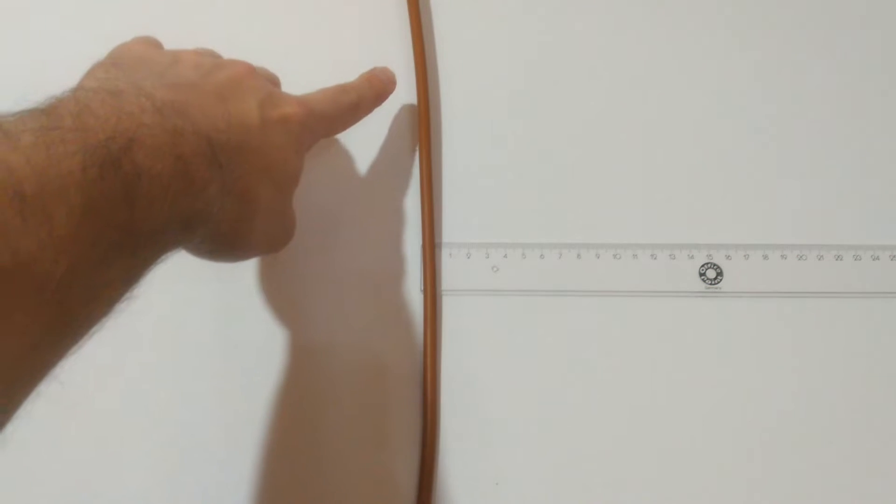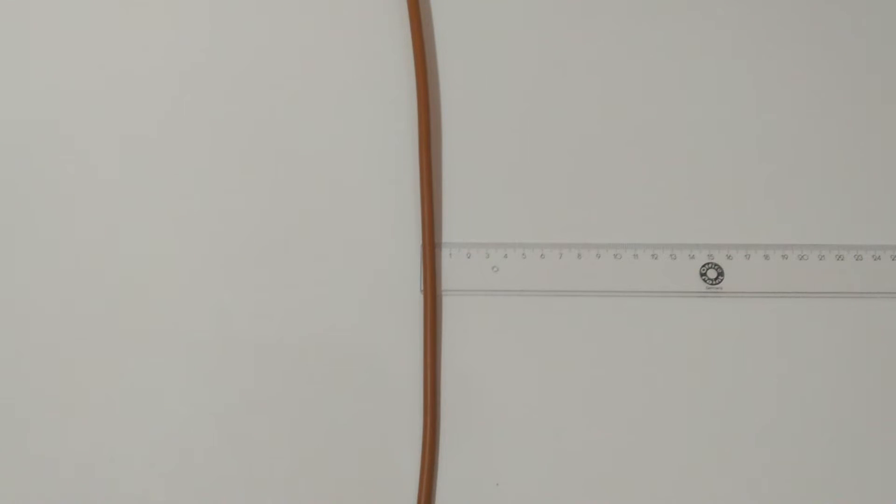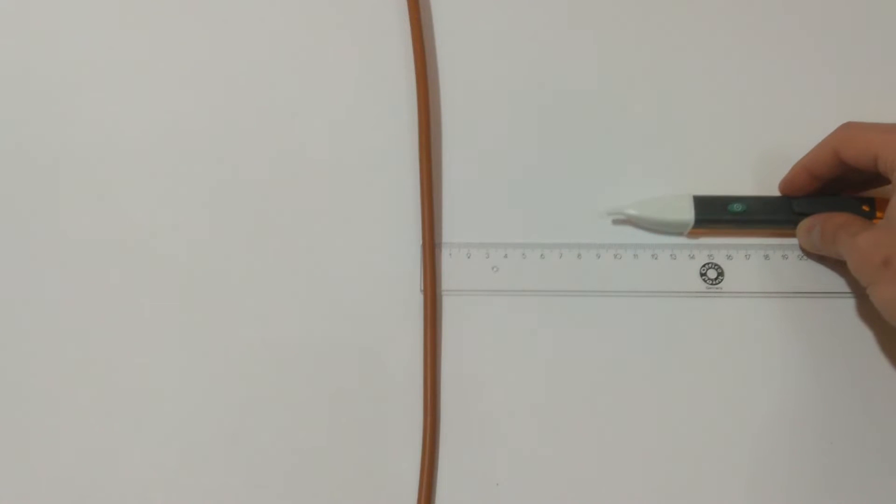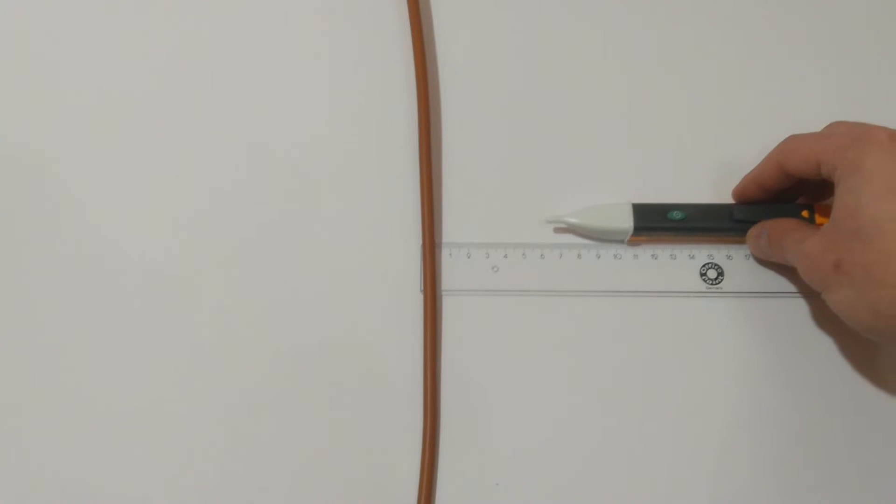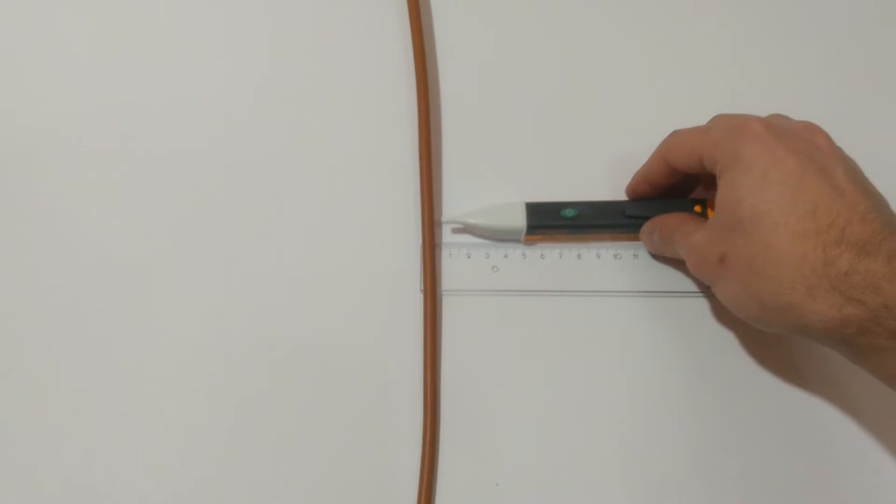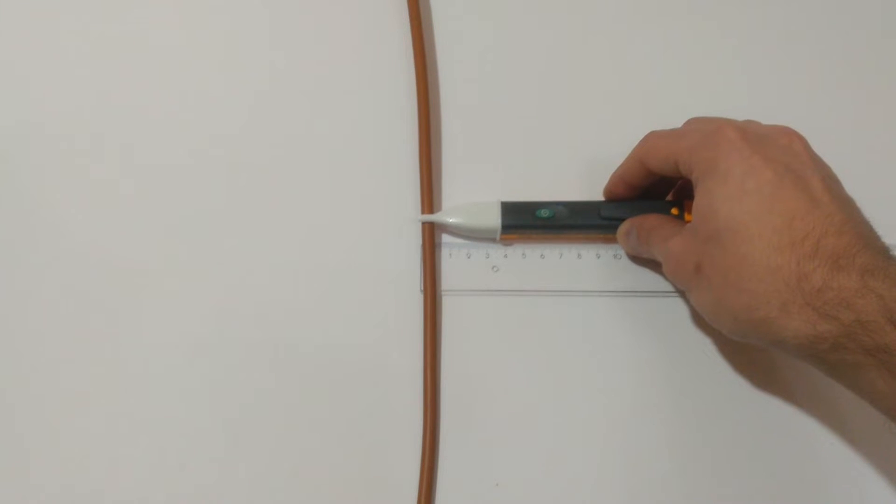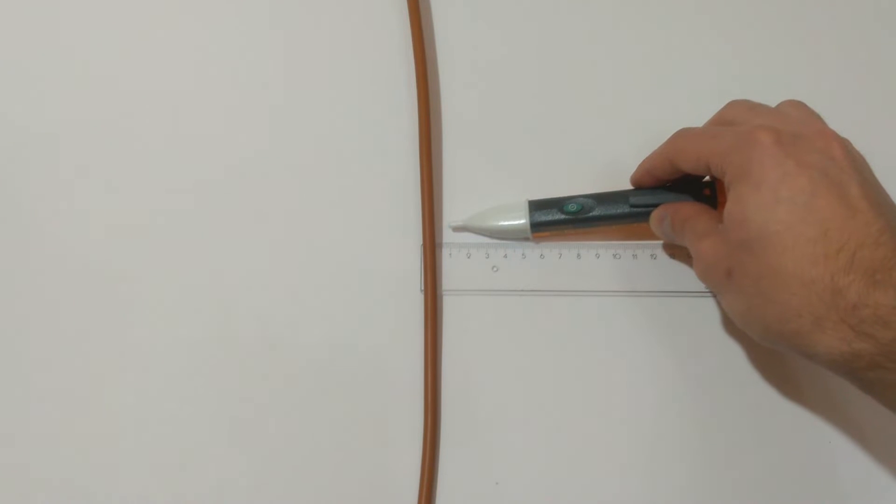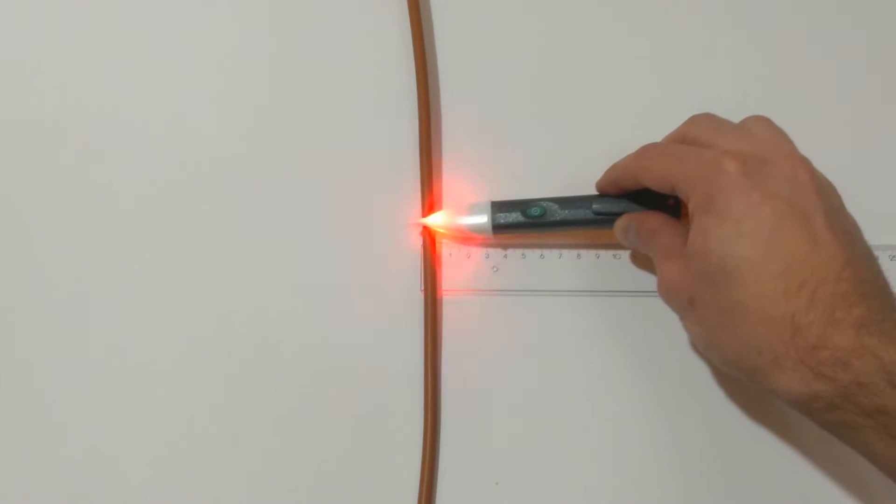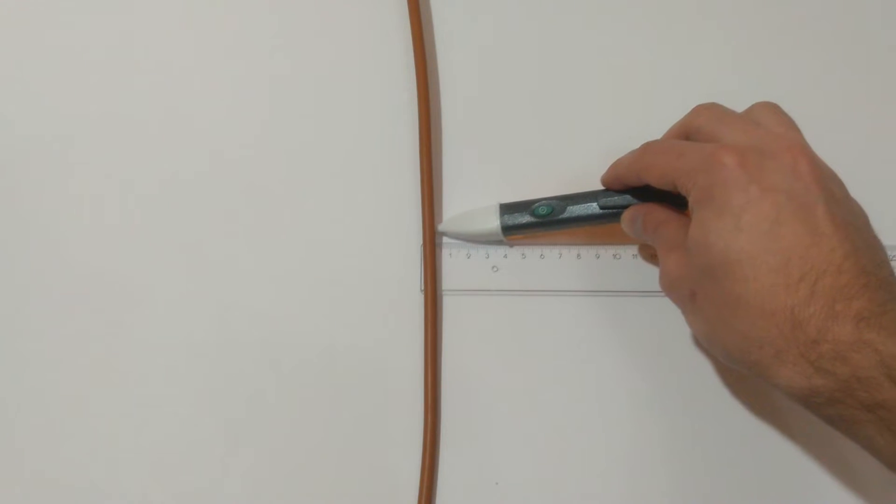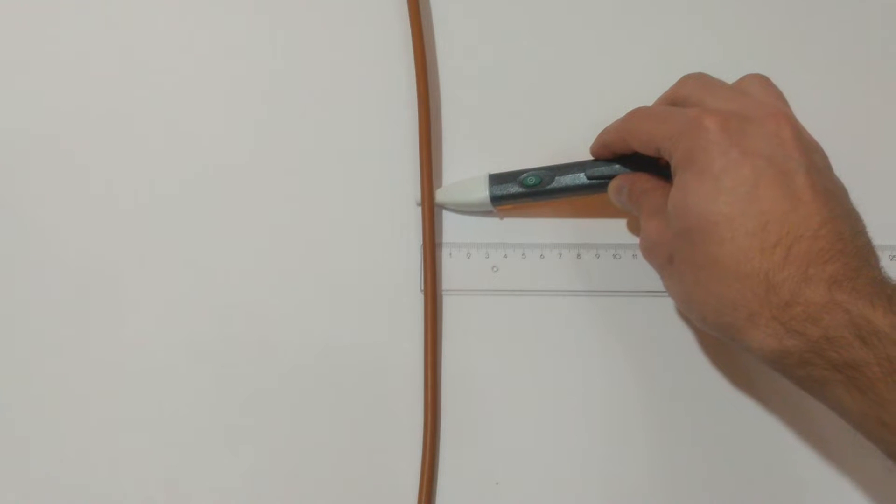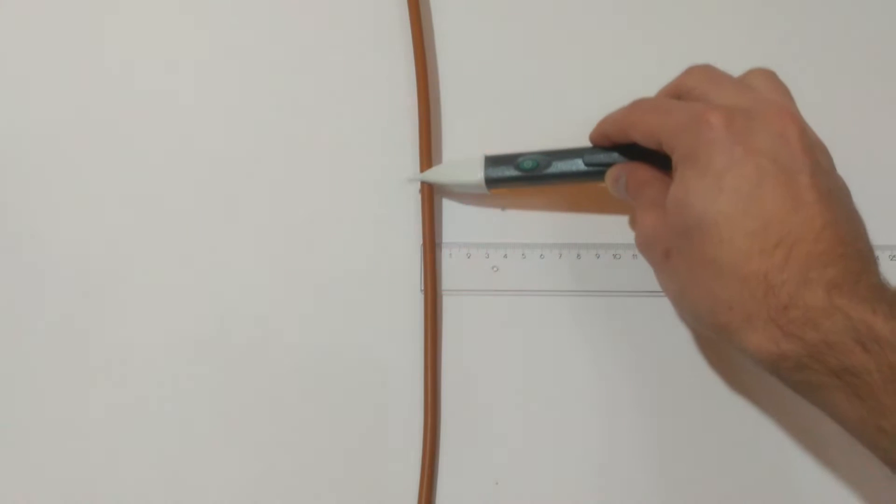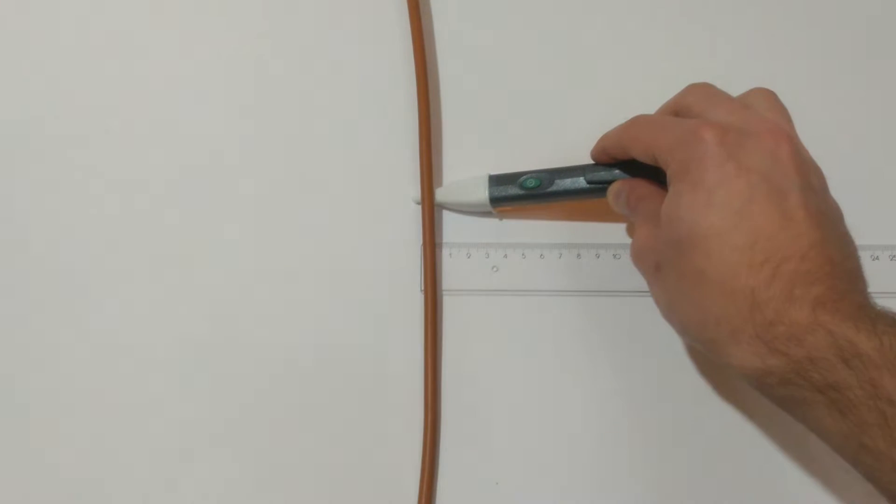Let's begin with the tests. Here I have this live circuit, this ruler. So the idea is to check which one of the voltage detectors will detect the live circuit from the greatest distance, starting with the Fluke. And it seems that you have to be extremely close to the live circuit for the Fluke to be able to detect it. And I mean extremely close.